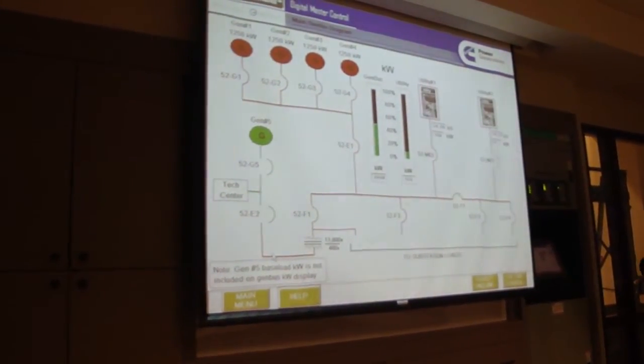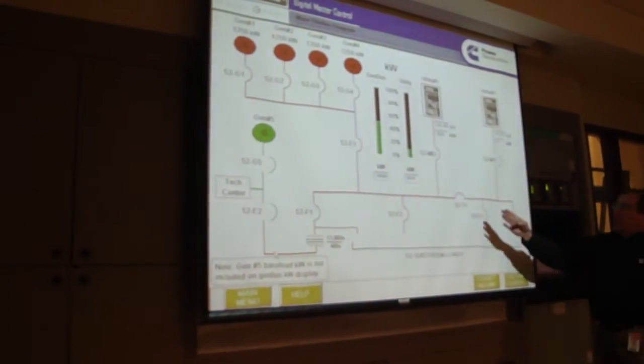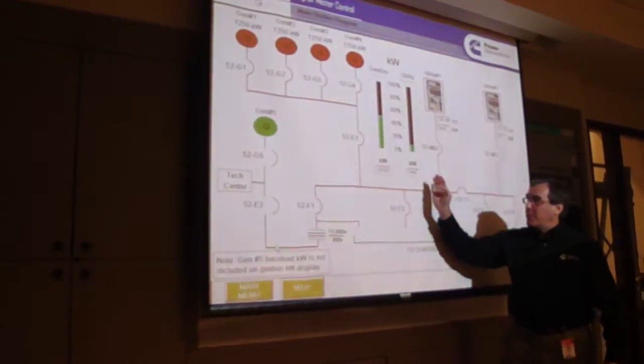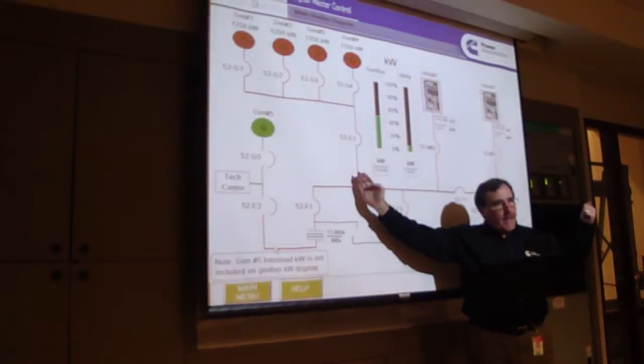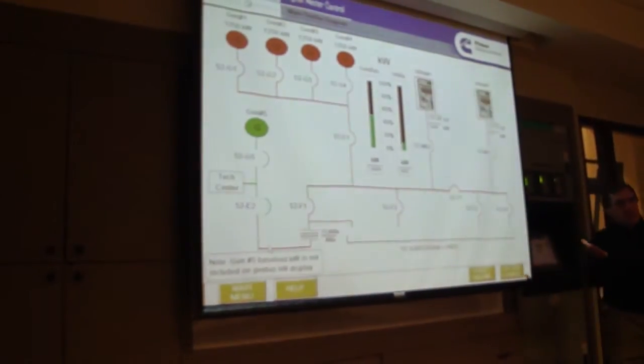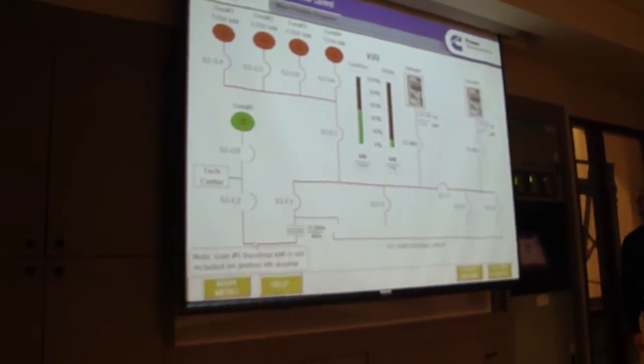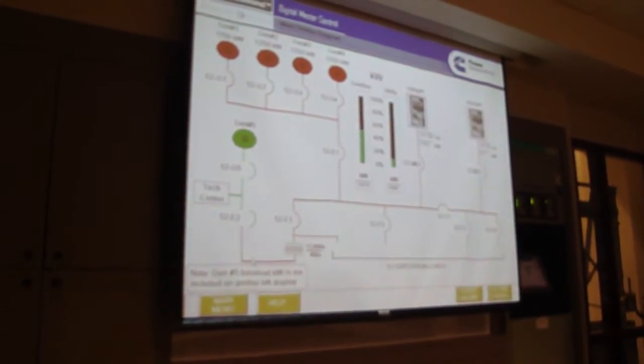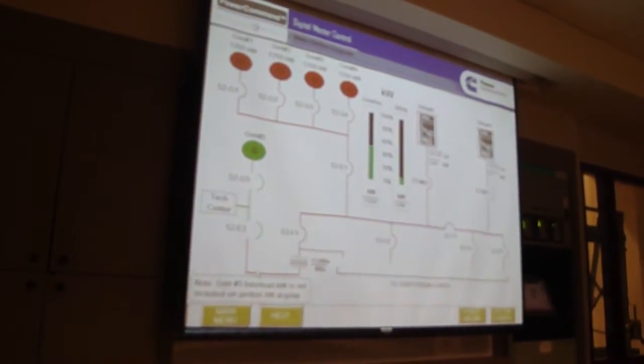Some of that is our timing — we set it up to allow us. What we do is soft ramping. We operate in parallel, we close, and then we pick up the load by basically stepping on the gas on the generators. And it just displaces the utility load. And the lights didn't flicker — that's a good thing.